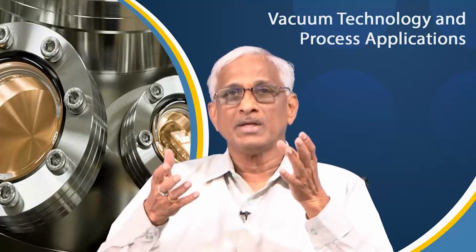Afterwards, you do not gain much. But very specialized applications like cryogenic freeze drying, etc., at very high vacuums, you have to maintain low temperature. That is a different special issue. So, most of the time medium vacuum is good enough for thermal applications, mechanical applications, suction applications, drying applications, etc.